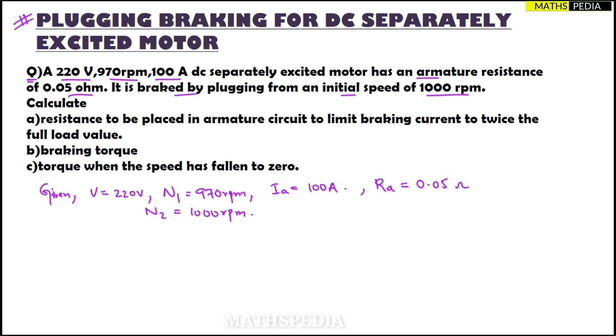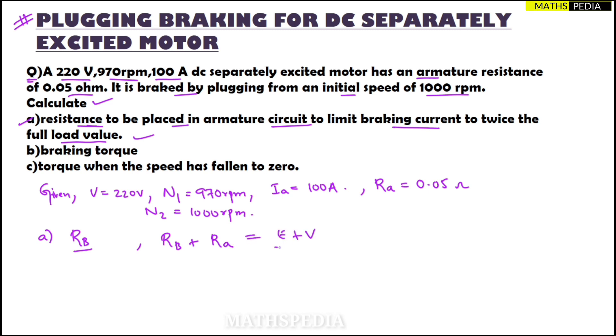In part one, we have to calculate the resistance Rb to be placed in the armature circuit to limit the braking current to twice the full load value. The formula is: Rb + Ra = (E + V) / Ia. This is similar to the basic resistance formula V/I, with the additional back-EMF term E.